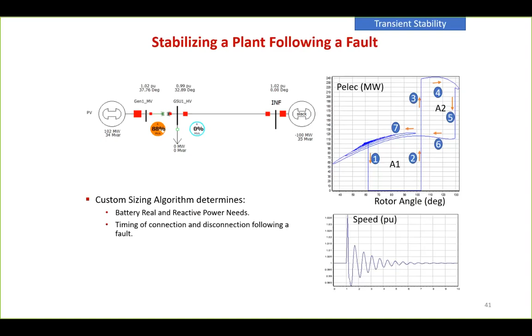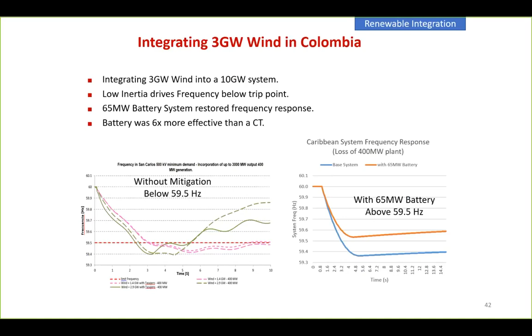Related directly to that, when we have a lot of wind in the system, we lose governor response. It's possible to get some synthetic governor response from wind turbines, but it risks breaking the blades, so the capability is limited. Storage is a great solution to provide synthetic governor response, and also something close to synthetic inertial response. These graphs show we can limit the frequency excursion by using a battery to replace the lost inertia and primary governor response. This means we don't have to redo the protection or worry about subsequent transient or dynamic stability problems. This is very real today, a commercial application.